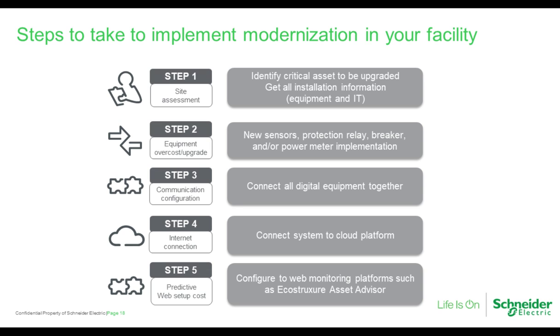Next is to take a look at other connected equipment that may also benefit from being connected. Knowing breaker and relay information can also be valuable data along with thermal readings to truly gain these insights needed to take action. With new sensors and protective relays, breaker and power metering implemented into the equipment, we can gather a lot more information as to what's going on with our system. With much of the old equipment, there's really not much information that we can gather, how the system's functioning, what its health is, what areas of maintenance, and again, what items really need to be replaced. That's why a full evaluation needs to be done of the existing equipment and see what condition that equipment is in, what needs to be upgraded, and also what needs to be monitored. The next step is the communication configuration. After the assessment, another equipment review involves connecting all the devices.